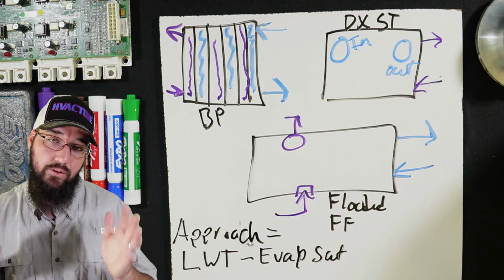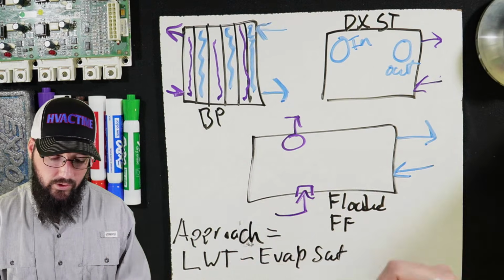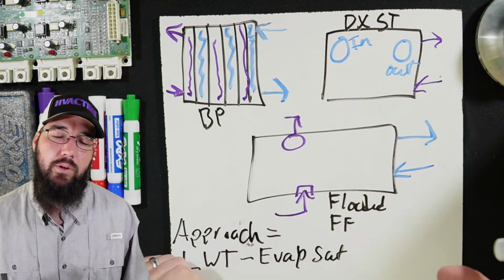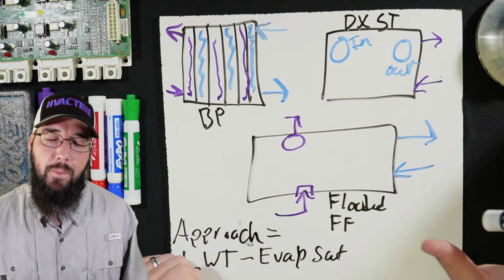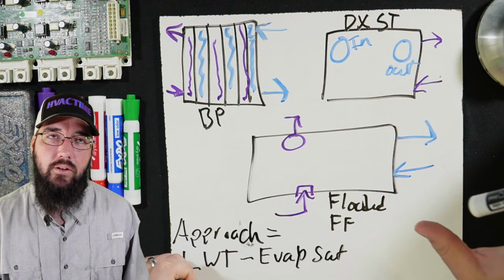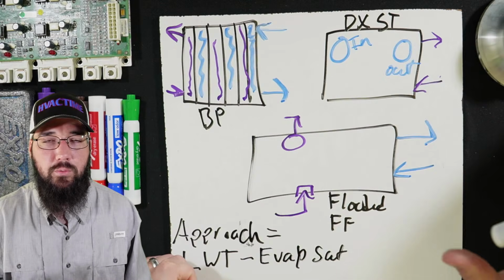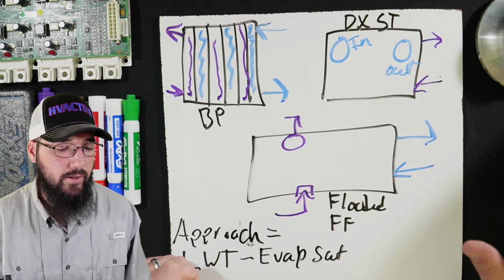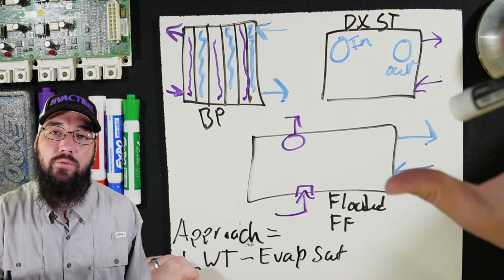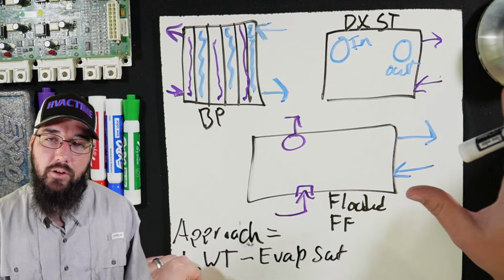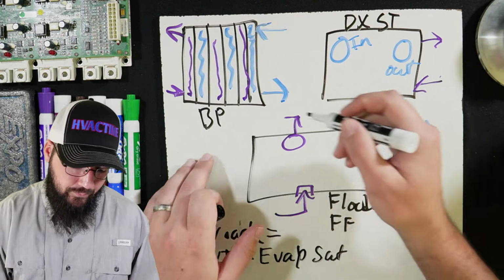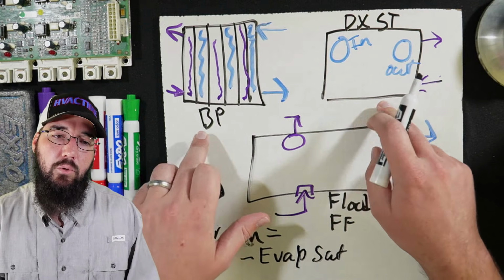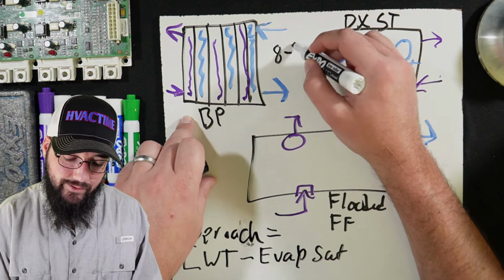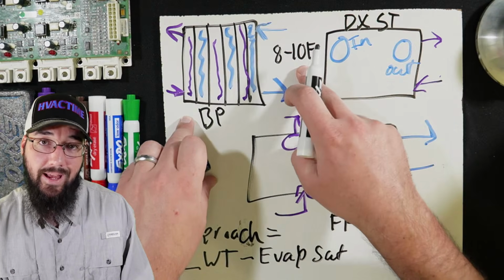All right, so the question is approach. Do they change? Yes. I will say this because factory guys give me grief about this all the time. Refer to your design data. Every machine is unique. They're all designed to do specific things. Let's see, what other lines am I supposed to say? Get it from your local service shop of whatever that model and serial is and follow that design data. Okay, now that that's out of the way, most of these evaporators for braze plate and DX shell and tube are going to be running an 8 to 10 degree Fahrenheit approach at full load. Okay, that is a critical point here.